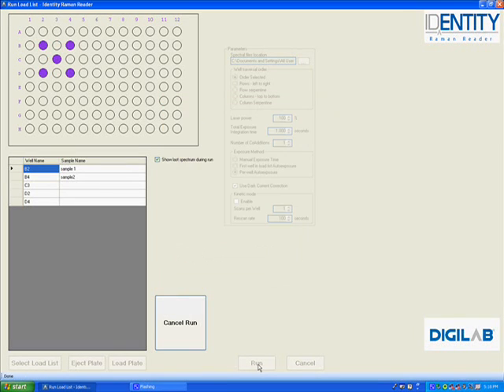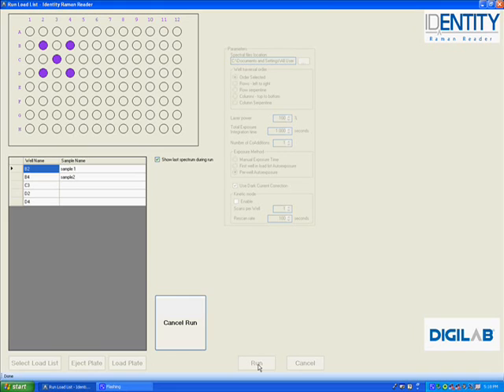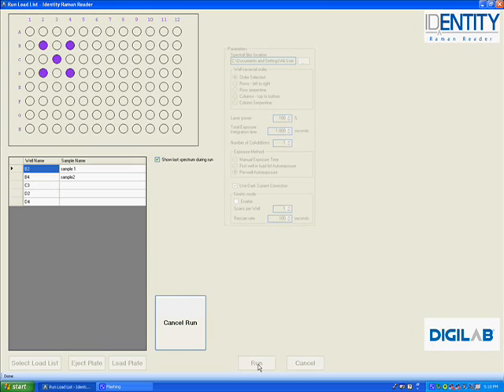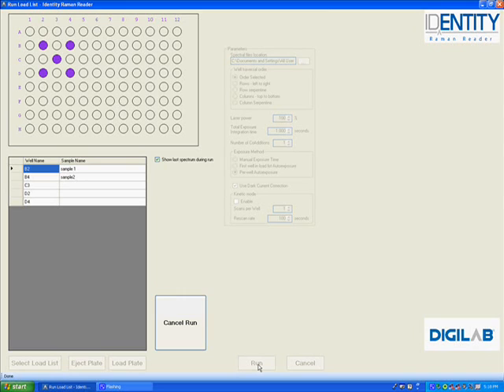We scanned all five wells with only about one second per well, so it's a very fast plate scan. To scan the entire plate in a one second per scan plate map view would take about five minutes. So within a very short period of time, we can collect data on 96 different samples with the spectra all being stored individually linked to the particular well position.